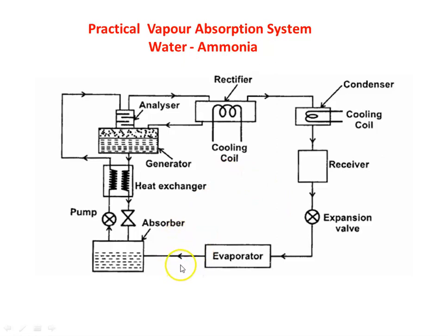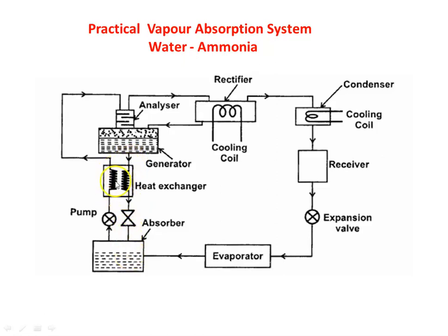Once again, we start from the outlet of the evaporator, where ammonia vapor is leaving. The ammonia vapor is mixed with water in the absorber, and an ammonia solution is formed. This ammonia solution, with lower temperature and higher concentration of ammonia, goes through the pump to the heat exchanger. In the heat exchanger, it absorbs heat energy from the other fluid — the hot ammonia solution flowing back from the generator toward the absorber.